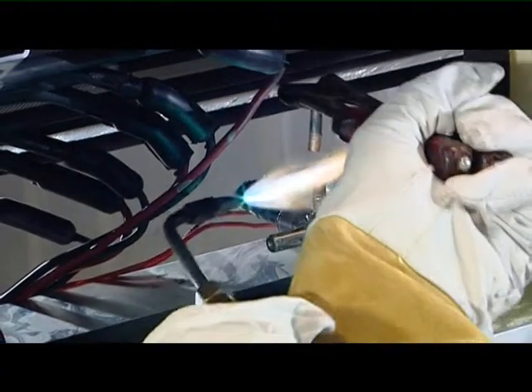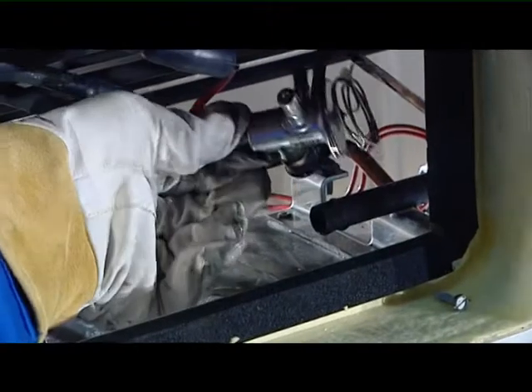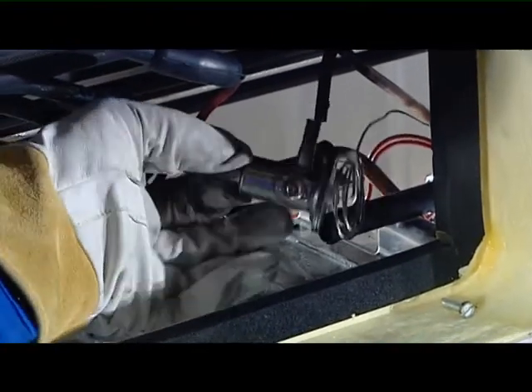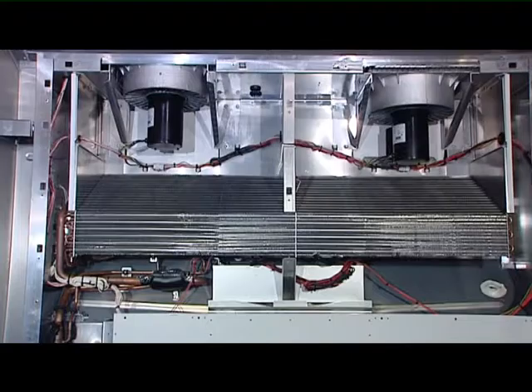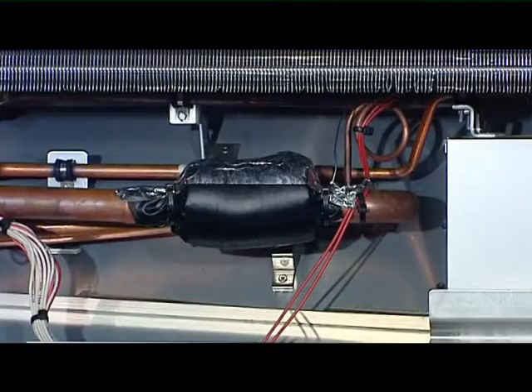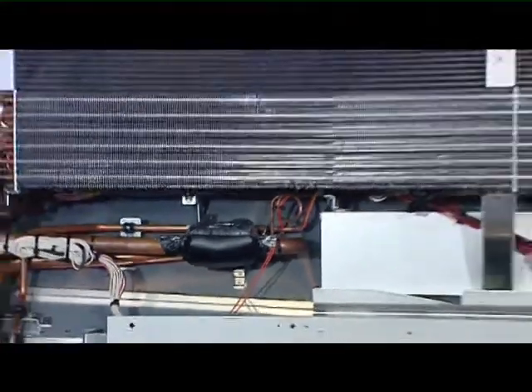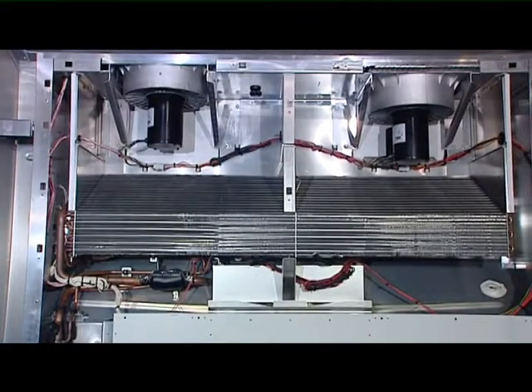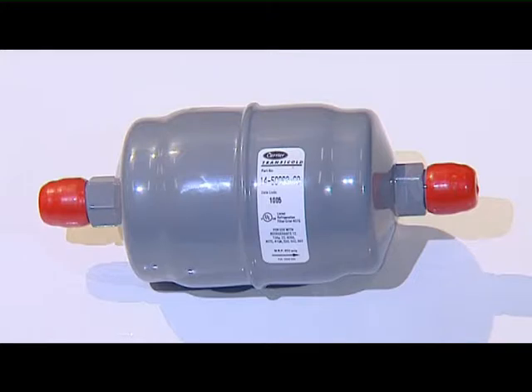Unbraze the valve's connections. Remove the valve and, in an emergency, simply cut the capillary tube. When fitting the new valve bulb, place it as far as you can reach, but it's very important to fasten it securely to isolate it. When replacing the TXV valve, always replace the filter dryer.